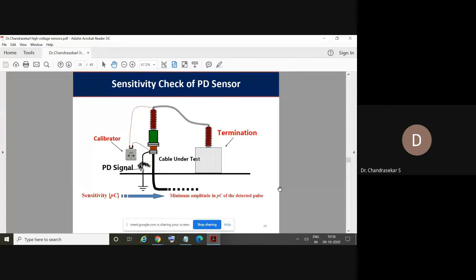In the evening, when we measured again at one particular termination, we got the same type of signals. We were really confused. Whether we were really measuring PD or what? Because it was a new place to us, we didn't know about it. We stayed one more day, and when we inquired about our problem with the concerned representatives of that place, they told us there is a small radio station 1 or 2 kilometers away. That radio station runs for 1 hour in the morning and 1 hour in the evening. So maybe you can cross-check, they told.